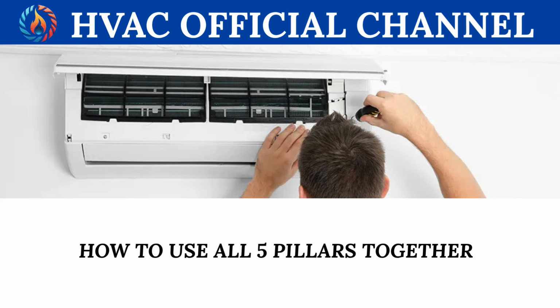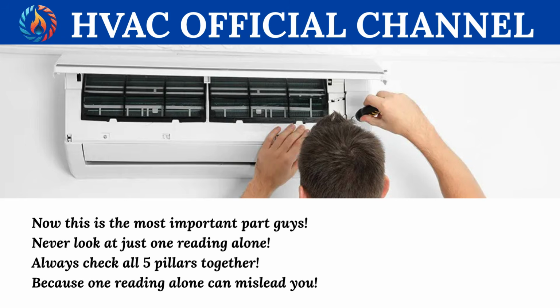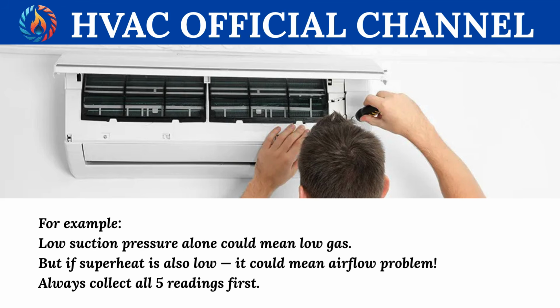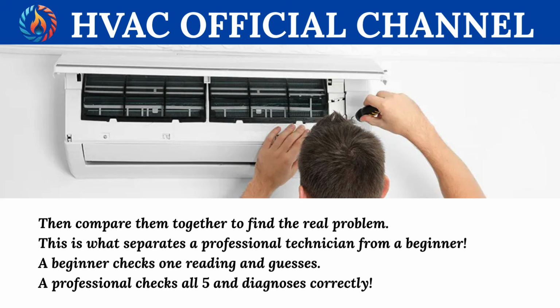How to use all 5 pillars together. Now, this is the most important part, guys. Never look at just one reading alone. Always check all 5 pillars together, because one reading alone can mislead you. For example, low suction pressure alone could mean low gas, but if superheat is also low, it could mean airflow problem. Always collect all 5 readings first, then compare them together to find the real problem.